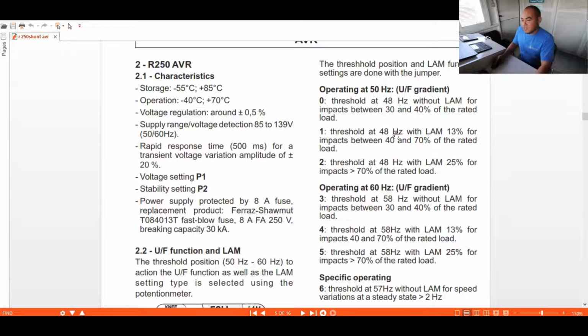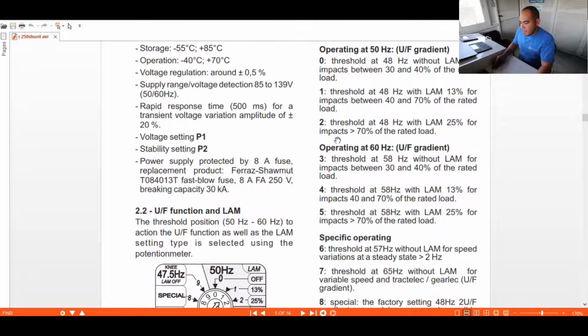Okay, so LAM connections. On the other side, number 2, threshold at 48 Hz with the LAM at 25%, it has an impact load of 70% of rated load. Let's summarize this one. At 48 Hz with LAM, if you set this one at 13%, you can gain 40 to 70% impact load of rated load. Without it, 30 to 40% impact of rated load. If you set this one to 25%, it will increase to 70% of your rated load impact.